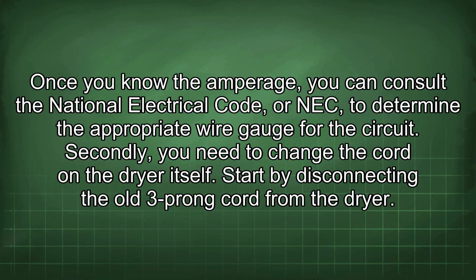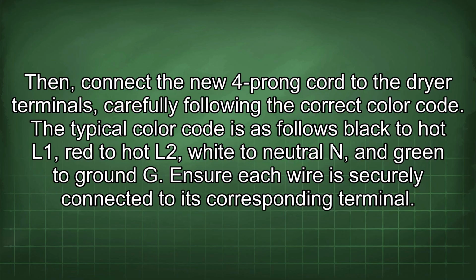Start by disconnecting the old 3-prong cord from the dryer. Then connect the new 4-prong cord to the dryer terminals, carefully following the correct color code. The typical color code is as follows: black to hot L1, red to hot L2, white to neutral N, and green to ground G. Ensure each wire is securely connected to its corresponding terminal.